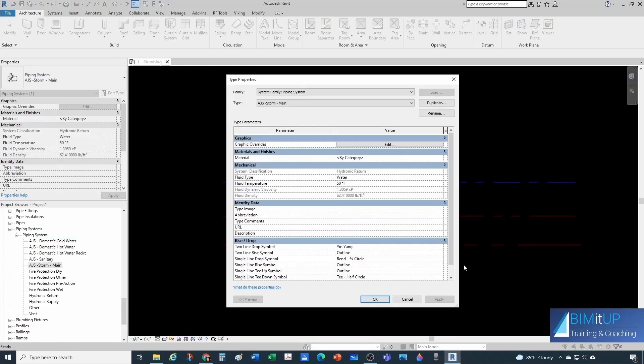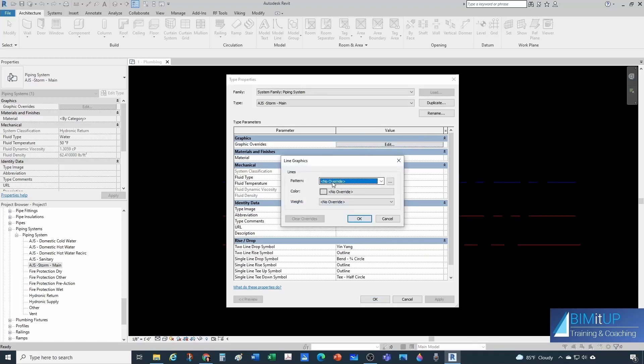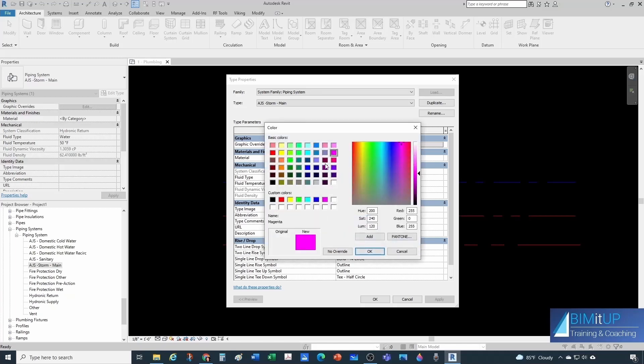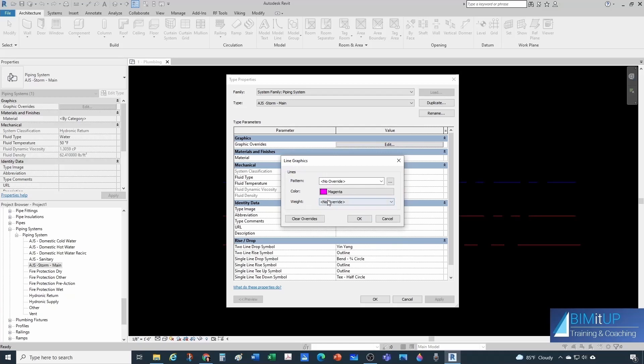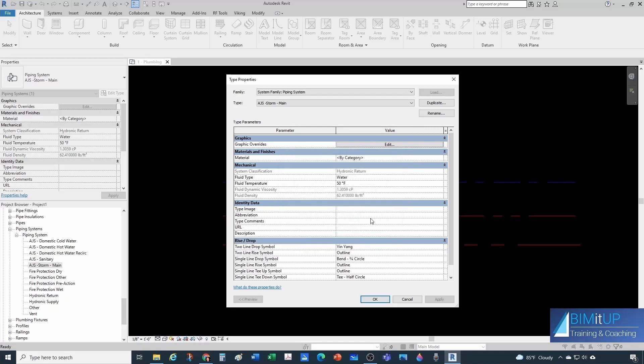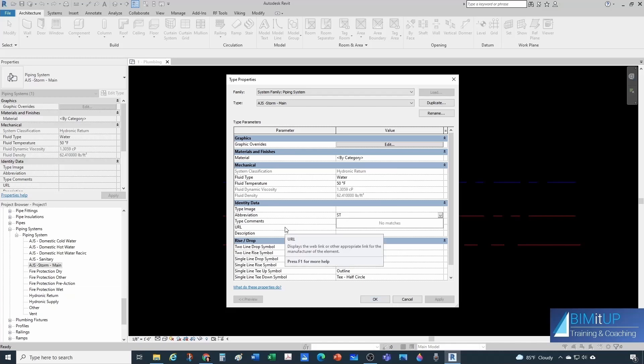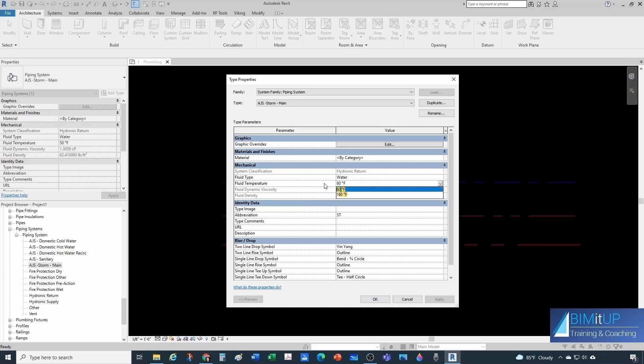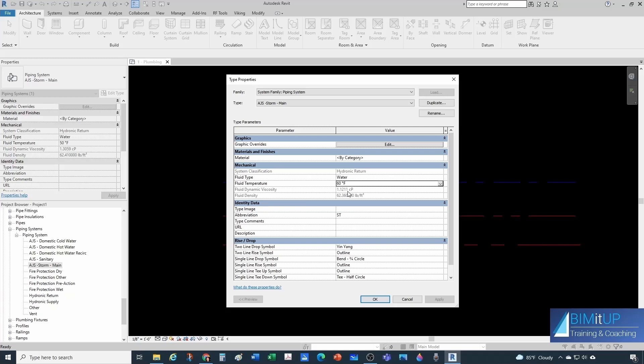I'll stand under Hydronic Return, duplicate it, and rename it 'AJS Storm Main' — because at some point I'll have a storm overflow system too. Under type properties: for graphic overrides I'll keep the standard solid line pattern; for color, pink; weight as standard with no overwrite. Under abbreviation I'll use 'ST'. For fluid type it's water; temperature maybe 60°F since I'm in Florida. This doesn't matter too much since I won't be calculating pressure drop — so I won't need viscosity or density.